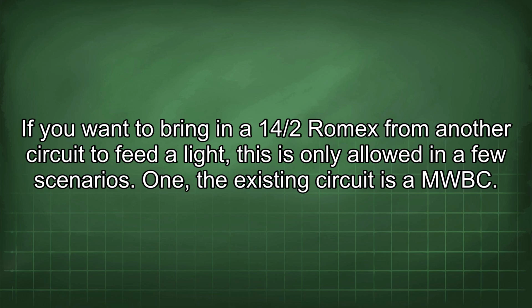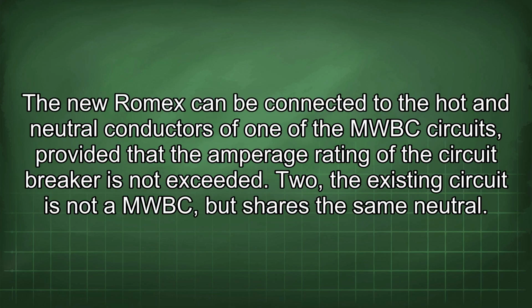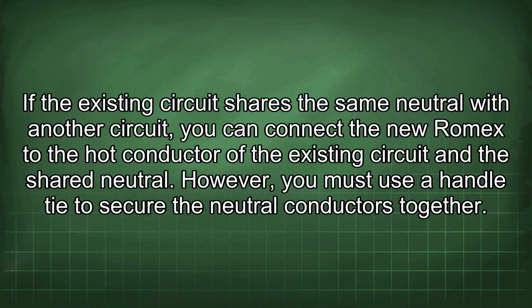The existing circuit is MWBC. The new Romex can be connected to the hot and neutral conductors of one of the MWBC circuits, provided that the amperage rating of the circuit breaker is not exceeded. 2. The existing circuit is not a MWBC but shares the same neutral. If the existing circuit shares the same neutral with another circuit, you can connect the new Romex to the hot conductor of the existing circuit and the shared neutral. However, you must use a handle tie to secure the neutral conductors together.